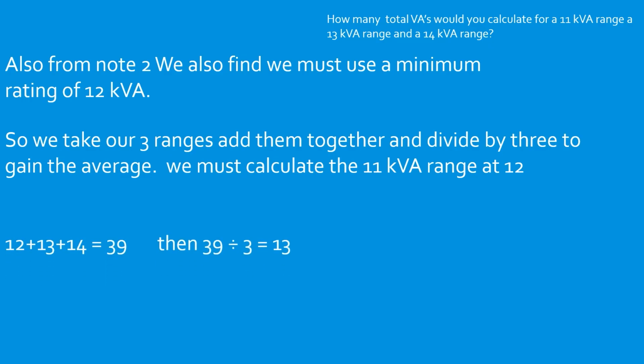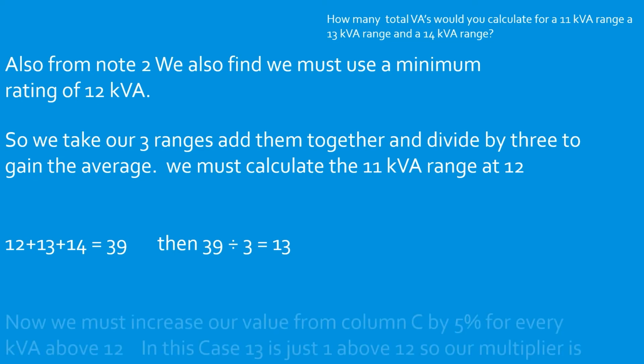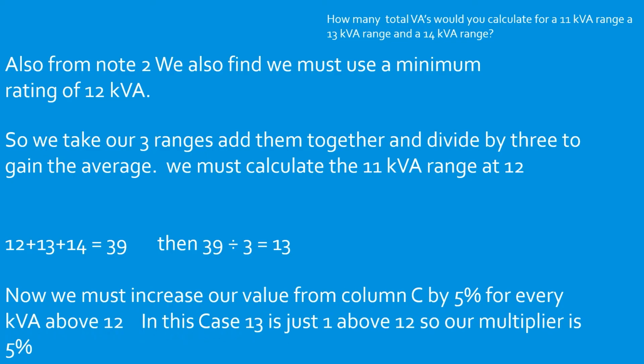So we take our ranges, we take 12, we take 13 and 14, and we add them together. Those are all the kVA values. That's going to give us 39 kVAs. Now we're going to take that 39 and divide it by the number of ranges. That's going to give us 13. Now what we do is we go back and we increase the column C value for that number of ranges by 5% for each one above 12. In this case, 13 is just one above 12, so our multiplier is 5%.